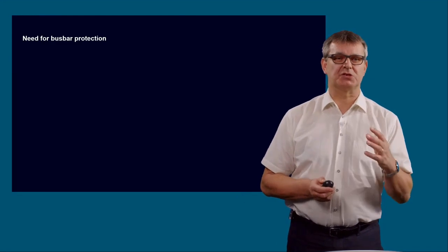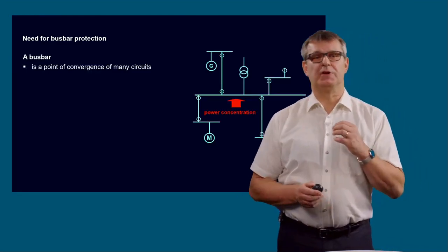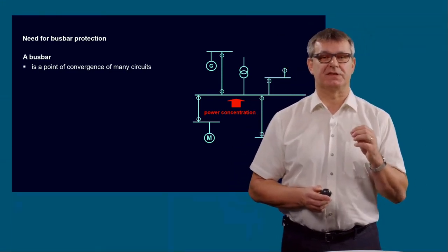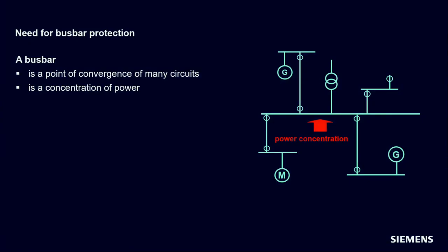That was for protection in general. Why do we need busbar protection? A busbar is really a point of convergence of many circuits. It's a concentration of power, and therefore really high and destructive fault currents can result. You can see this in this very small single line diagram. Single busbar, we have several generators, we have several consumers like motors in this case, and we also have transformers to a lower busbar voltage level. And so here the busbar is a very high point of convergence, a high concentration of power.